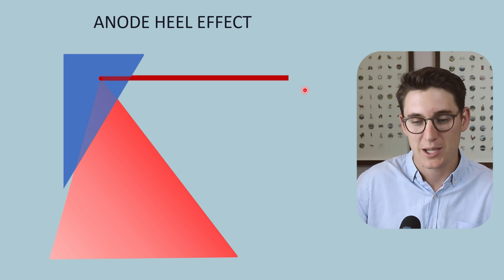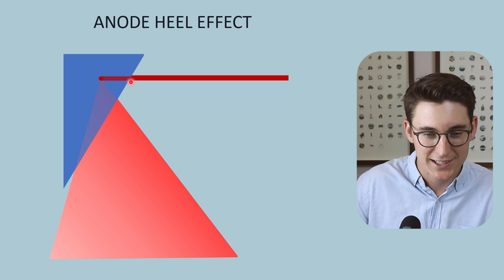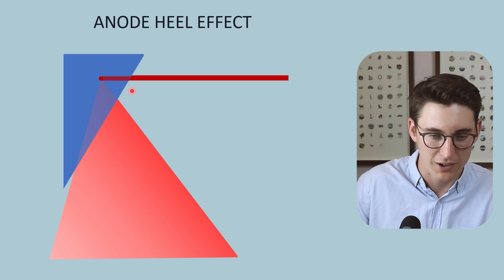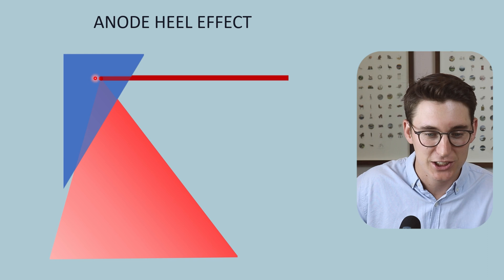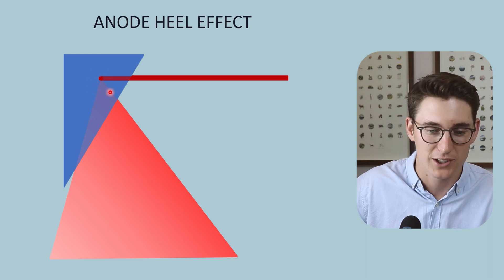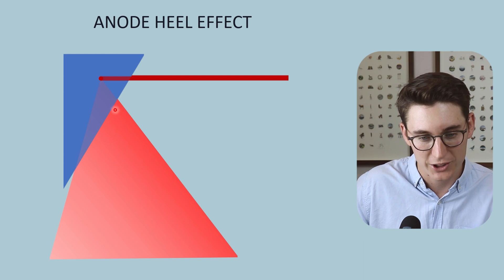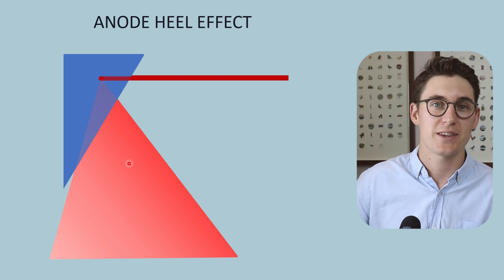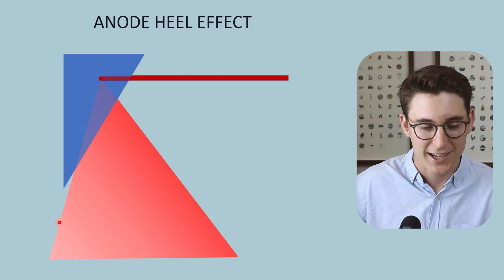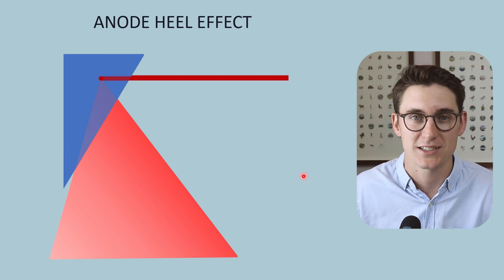Now a common misconception is that our electron beam hits our anode and forms x-rays on the surface of our anode. The x-rays are actually formed within our anode here. And it's because these x-rays have to travel through differential distances depending on whether they're on the anode or the cathode side. It leads to this variation in x-ray beam intensity.